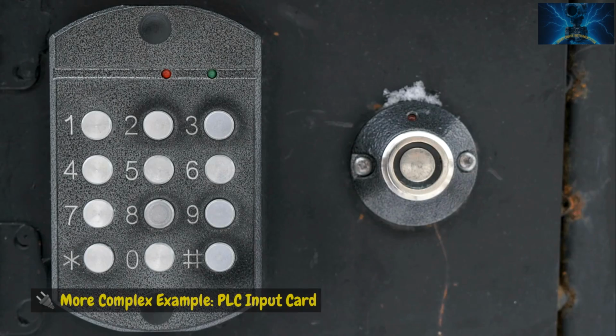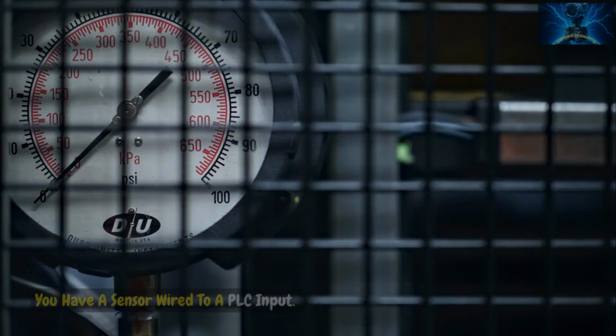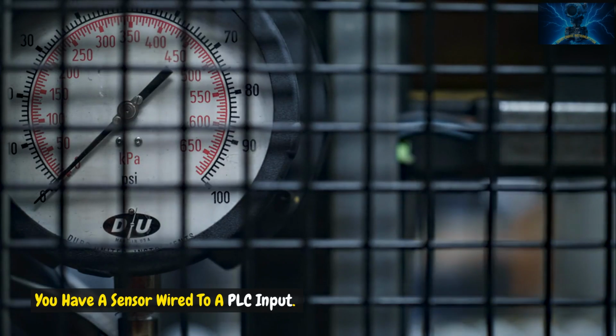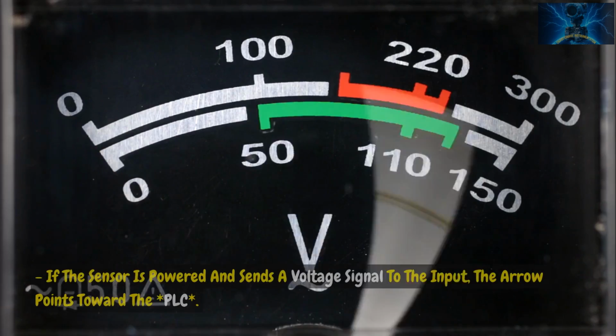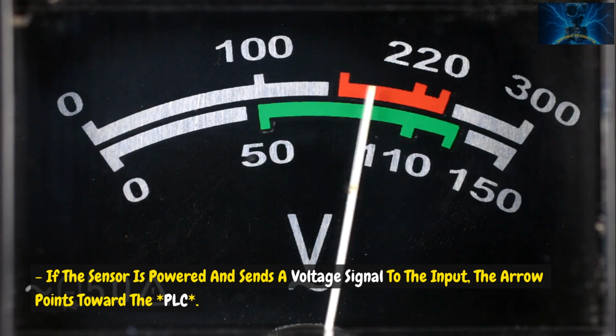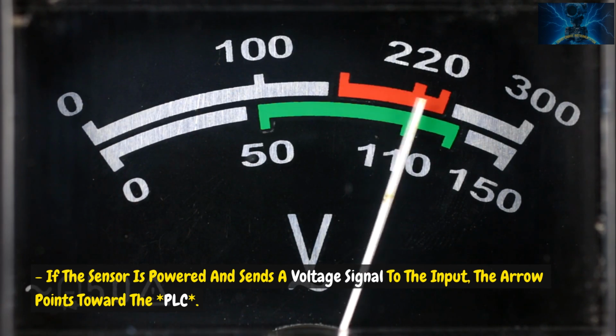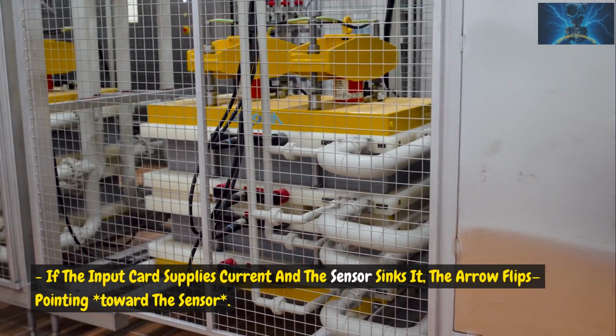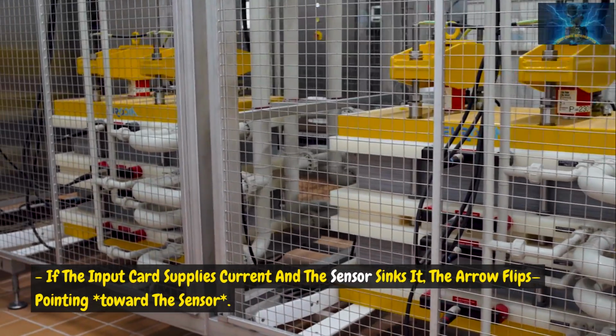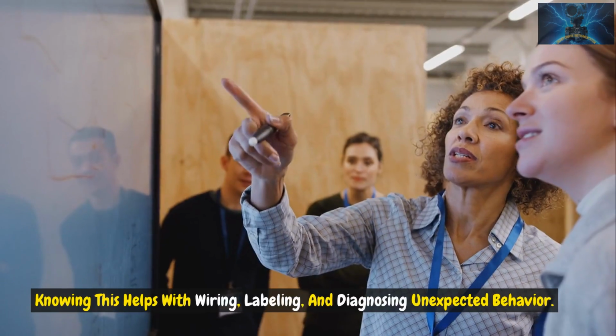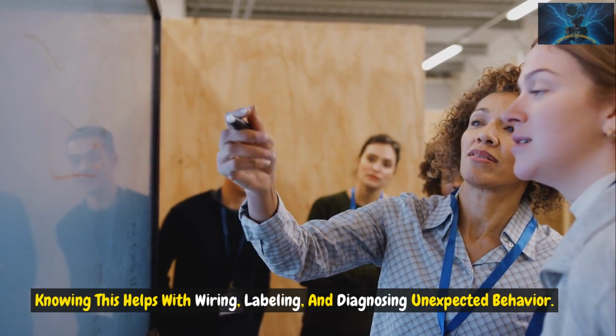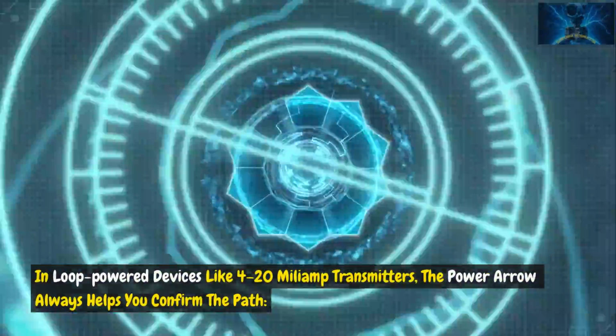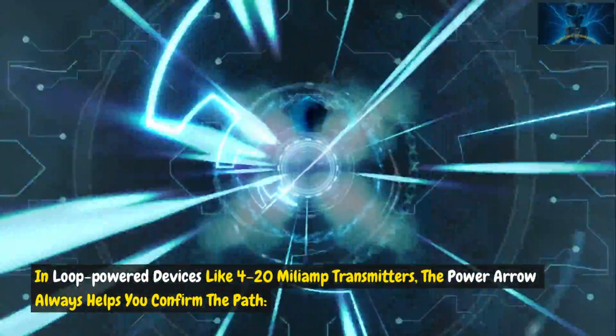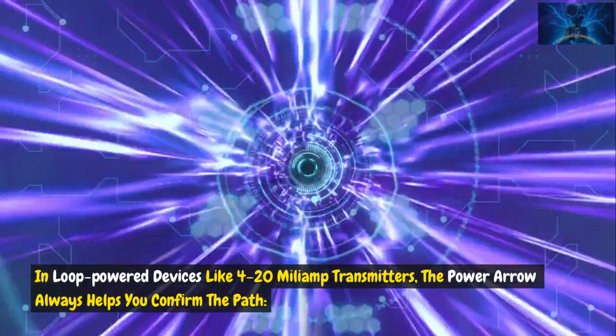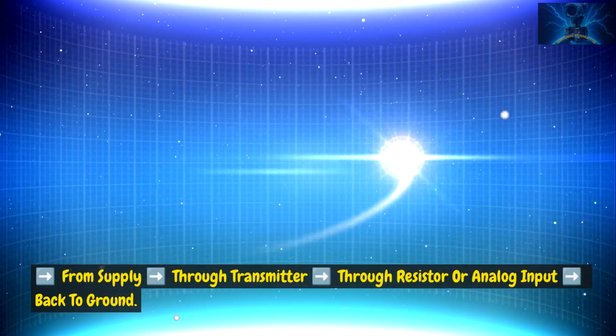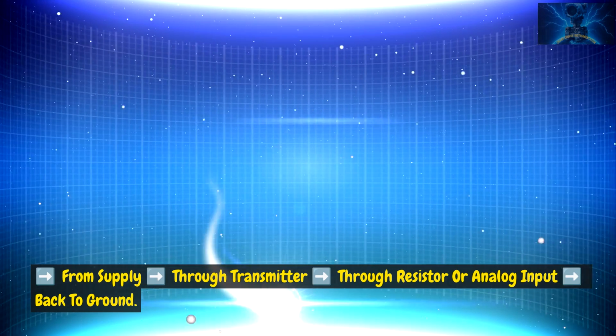More complex example, PLC input card. You have a sensor wired to a PLC input. Which way is the energy flowing? If the sensor is powered and sends a voltage signal to the input, the arrow points toward the PLC. If the input card supplies current and the sensor sinks it, the arrow flips, pointing toward the sensor. Knowing this helps with wiring, labeling, and diagnosing unexpected behavior. In loop-powered devices like 4 to 20 milliamp transmitters, the power arrow always helps you confirm the path: from supply, through transmitter, through resistor or analog input, back to ground.